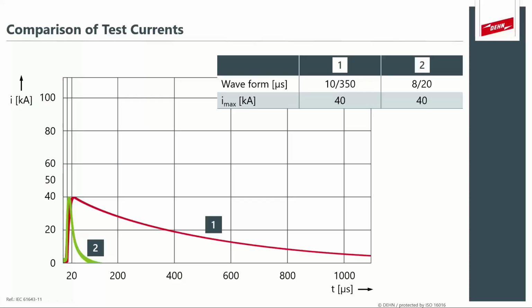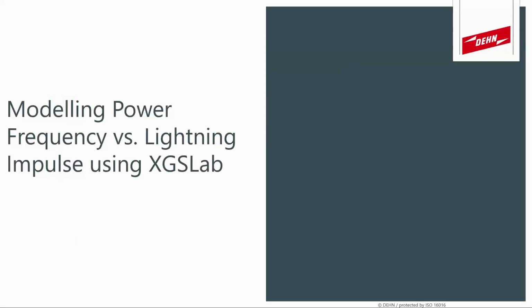So if we want to investigate or calculate the energy associated with these waveforms, we take the integral, or the area under the curve, and you can immediately see that the area under the red curve is much larger than the area under the green curve. And that's why these direct lightning strikes cause so much more damage, and carry so much more energy compared to a surge. Now, all these aspects need to be taken into consideration when we are modeling for a first positive or a first negative. What's the peak value, and what's the shape of the impulse that we're injecting? The next few slides will explain how we model power frequency versus lightning impulse using XGSLab.